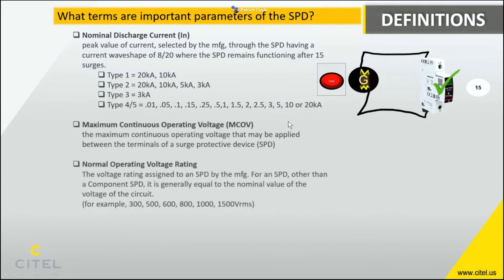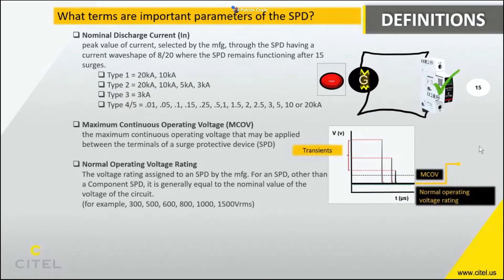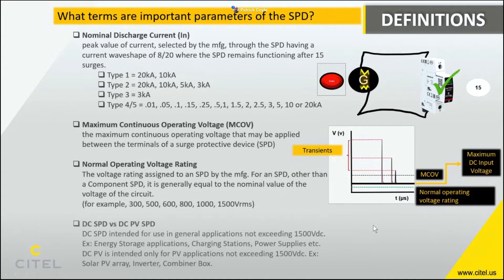The next two interrelated terms are very important when selecting the appropriate SPD for any system: maximum continuous operating voltage or MCOV, and the normal operating voltage. MCOV is related to the minimum turn-on voltage of the surge protector, and the normal operating voltage is the nominal voltage of the circuit. In DC power — like rail applications — there may be a steady nominal voltage, but we want to know what the peak voltages can potentially be.